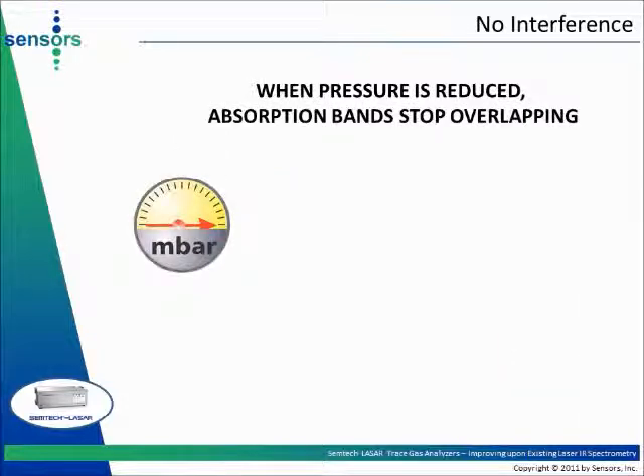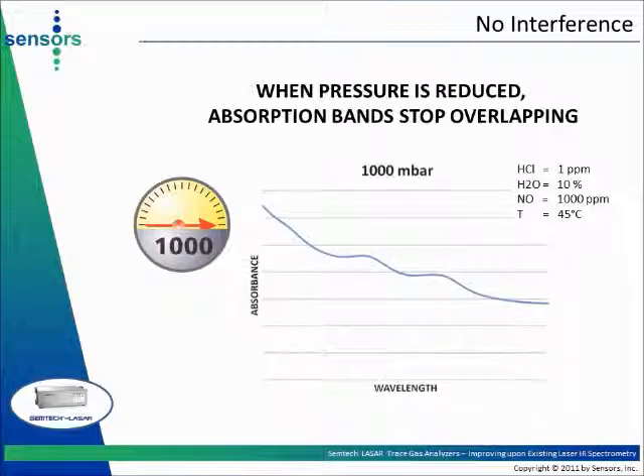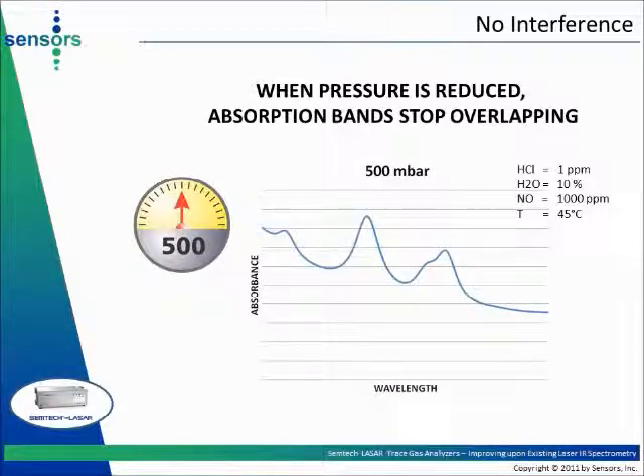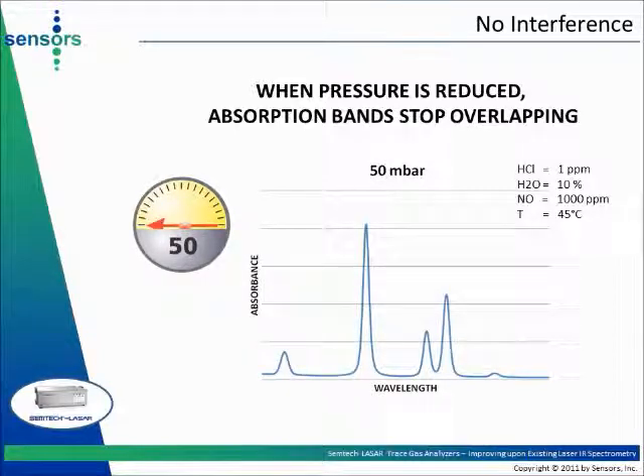When gas pressure is lowered inside the gas cell, the bandwidth of the absorption bands is reduced. As an illustration, this slide shows the spectrum of a mixture of 1 ppm of hydrochloric acid (HCl), 1,000 parts per million of nitric oxide (NO), and 10% volume of water vapor measured at 45 degrees C. At atmospheric pressure (1,000 millibar), absorption bands overlap. When lowering the pressure to 500 millibars, absorption bands begin to resolve. As pressure is further reduced to 50 millibars — one twentieth of atmospheric pressure — absorption bands are clearly resolved from each other with no spectral overlapping.